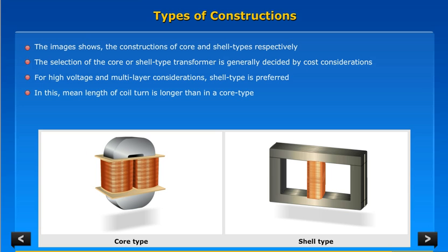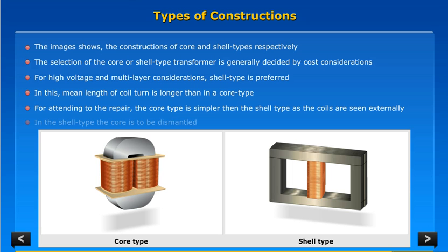In this, the mean length of coil turn is longer than in a core type. For attending to the repair, the core type is simpler than the shell type as the coils are seen externally. In the shell type, the core is to be dismantled.